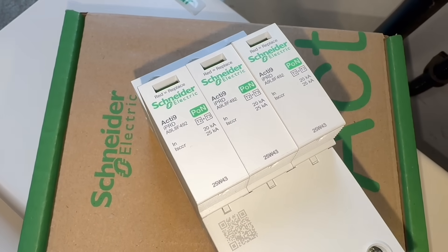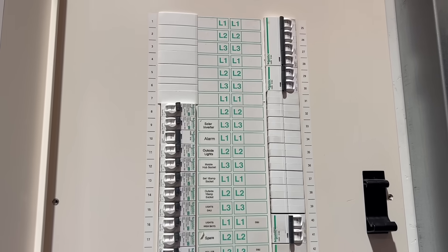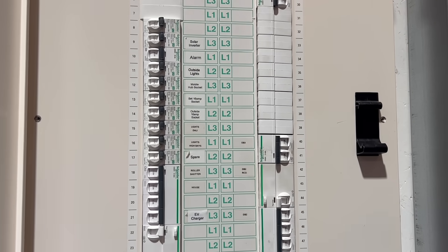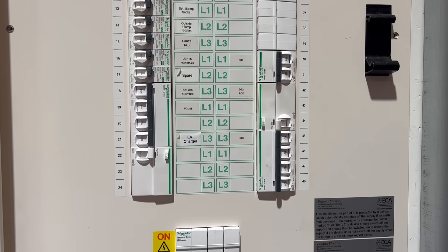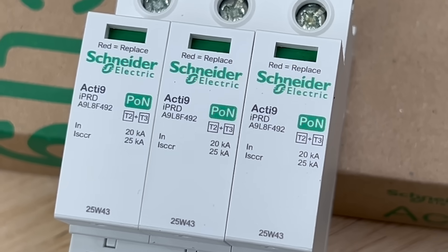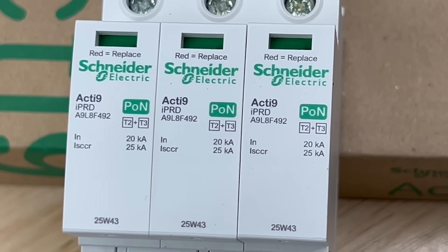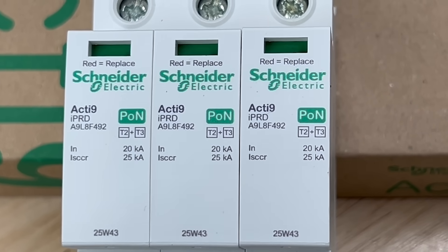The device connects directly to the bus bar and the entire solution fits neatly inside the distribution board using just three modules, even on a three-phase system. Less wiring, less hardware, and a much cleaner install. The Schneider Acti9 isobar and KQ distribution boards are some of the most popular commercial boards out there, installed in thousands of installations. The good news is that these new surge protection devices are backwards compatible, which means they can be added easily to existing boards, not just new builds.